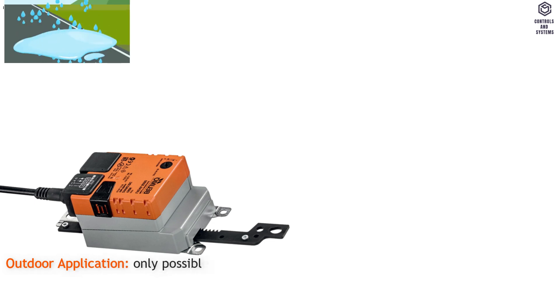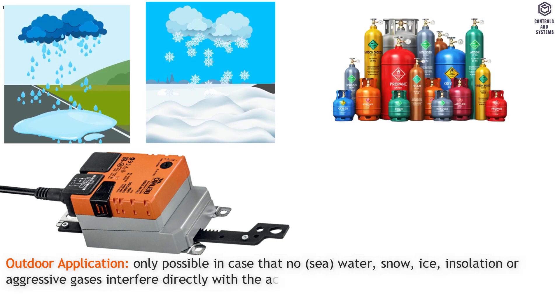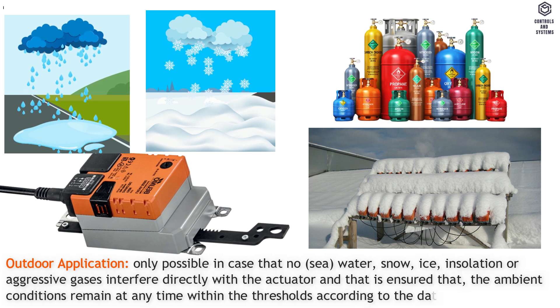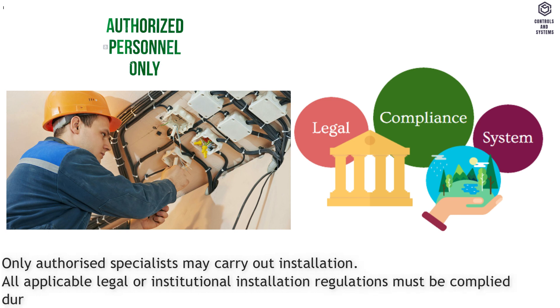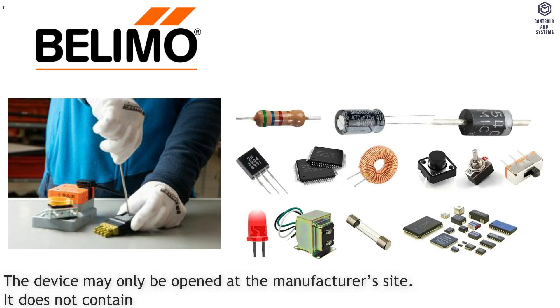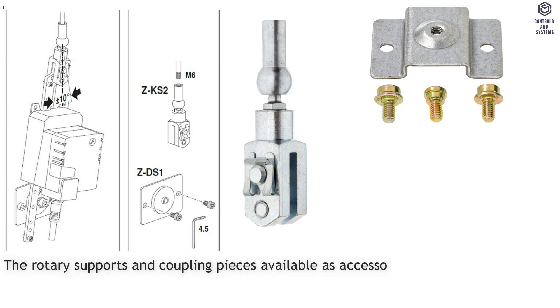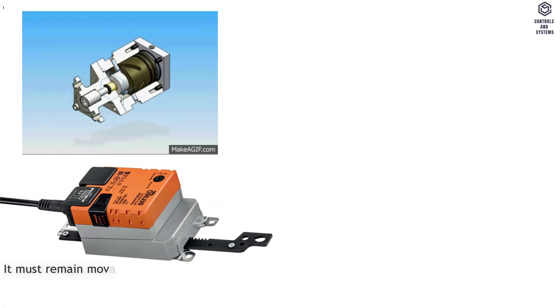Safety notes. Outdoor application is only possible in case that no sea water, snow, ice, insolation, or aggressive gases interfere directly with the actuator, and it is ensured that the ambient conditions remain at any time within the thresholds according to the datasheet. Only authorized specialists may carry out installation. All applicable legal or institutional installation regulations must be complied with during installation. The device may only be opened at the manufacturer's site and does not contain any parts that can be replaced or repaired by the user. The rotary supports and coupling piece must always be used if transverse forces are likely, and the actuator must not be tightly bolted to the application — it must remain movable via the rotary support.